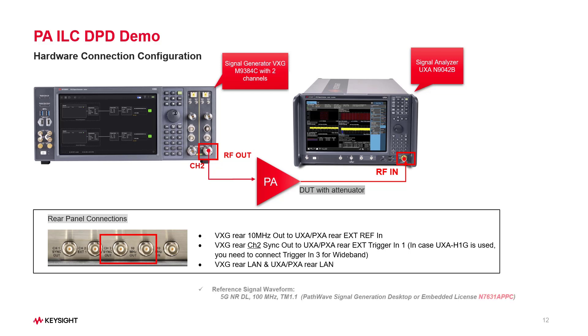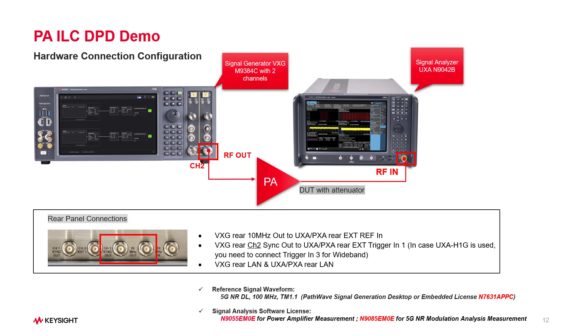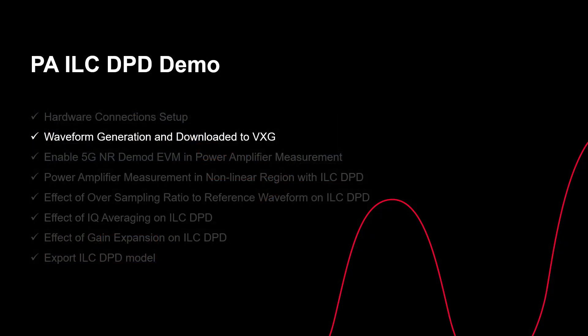After hardware connections, you need to prepare the reference signal waveform. You can use PathWave signal generation desktop or embedded software version with N7631A license to generate a 5G signal, or you could prepare your own waveform. To see how to generate a 5G signal using PathWave signal generation desktop, please go to the link in the description box. One more thing: if you want to get 5G demod EVM results during the Power Amplifier measurement, you need to have the 5G NR analysis measurement application license as well. Now we are ready to download the reference waveform to the VXG.